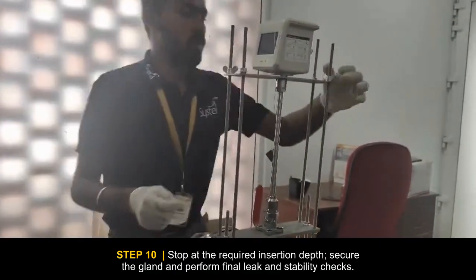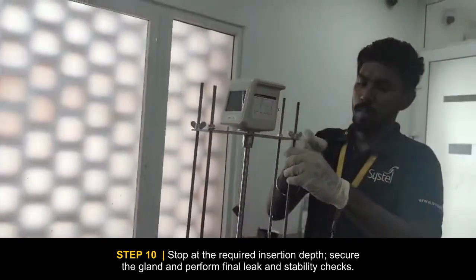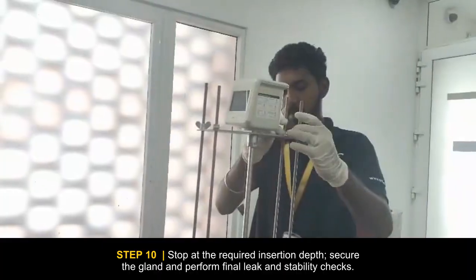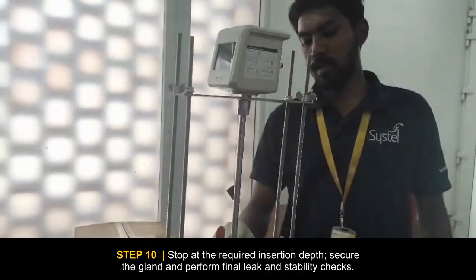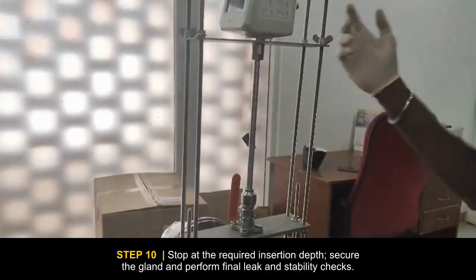Stop when the specified insertion depth is reached. Secure the compression gland and lock nut, then complete the required leak test and final stability check before placing the sensor in service.